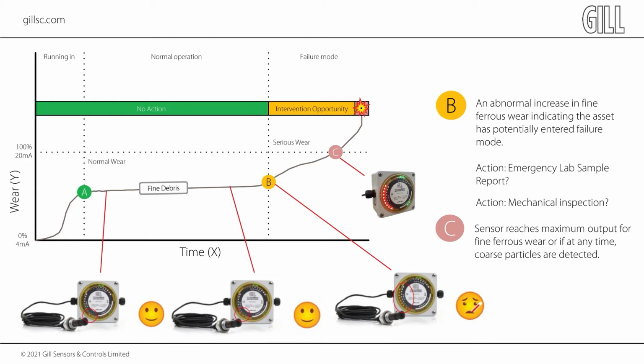within the gearbox system. Maybe there is water ingress, maybe it's a lack of lubrication, maybe it's something else. What this does mean is a call to action for maintenance personnel to inspect the gearbox. If caught early enough, a scheduled maintenance action can be taken and unexpected downtime can be avoided.